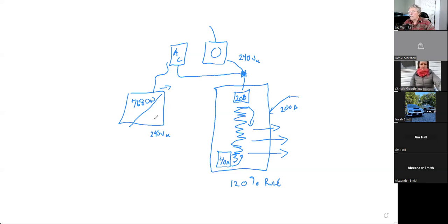But if the system is bigger, let's say I've got a 10 kW system here, and I just simply can't hook in here without replacing this whole unit, I might just do a supply side connection. So those are the two different types: load side and supply side. Supply side's always going to be a bit more expensive.